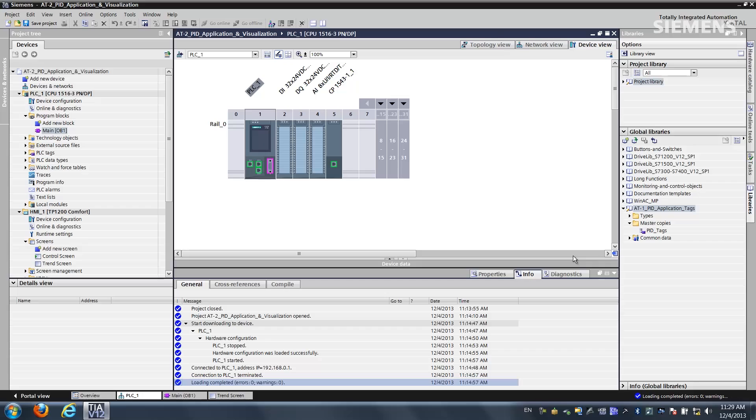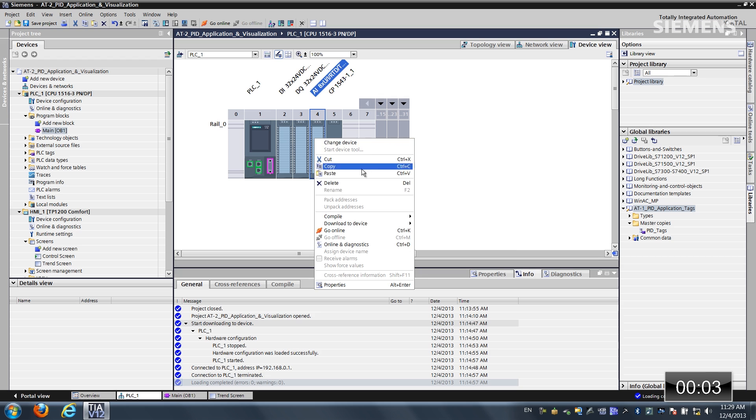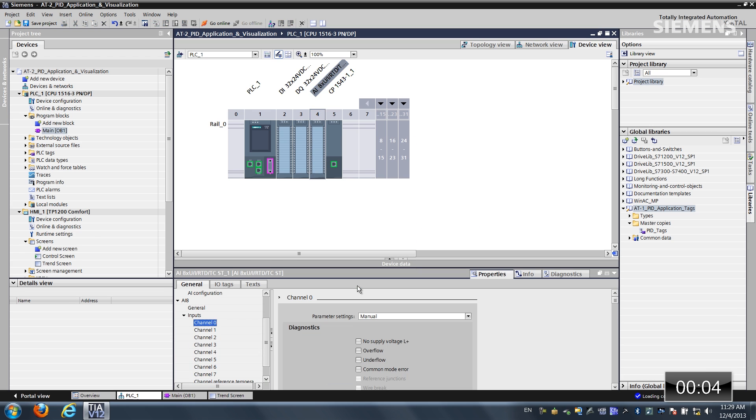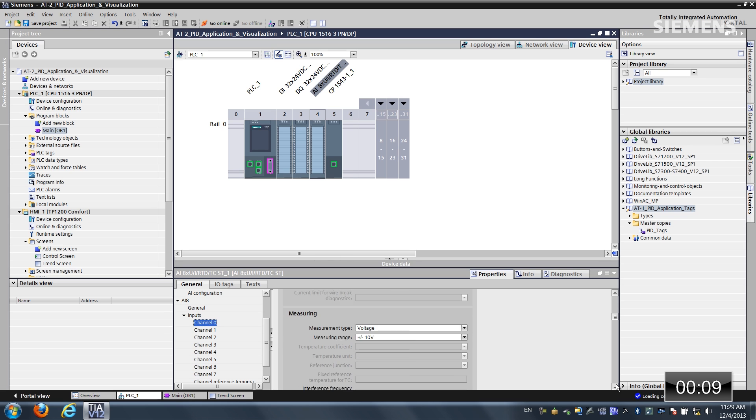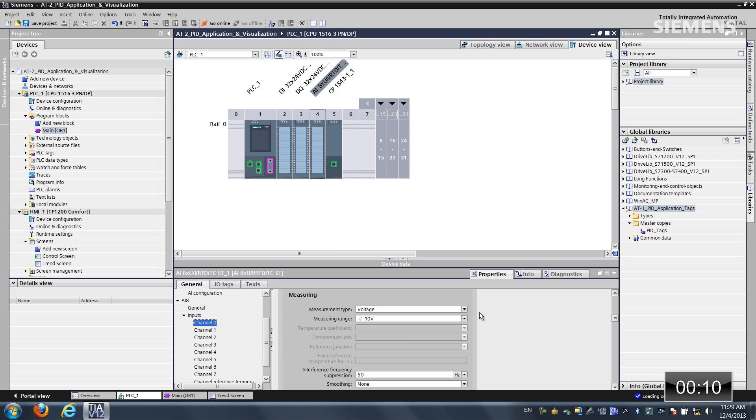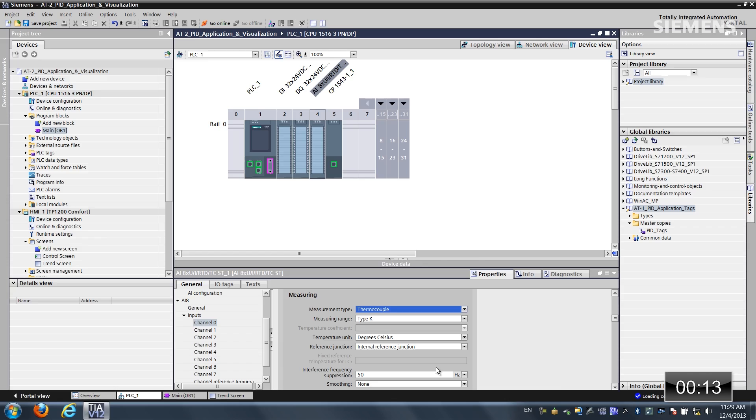The first step is, here in the hardware configuration section, I want to give focus to our analog card, right click and choose properties. Channel 0 is where the thermocouple is wired into, so I want to go down to the measurement section of this channel and change it from voltage to thermocouple.